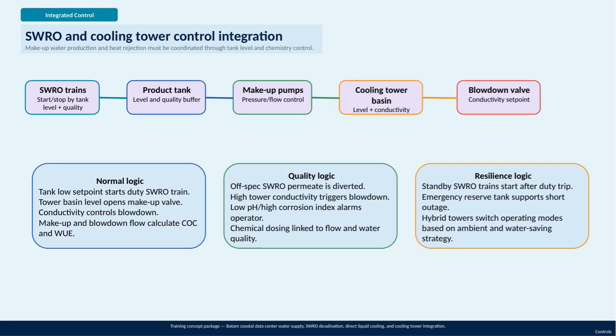The normal operating logic activates a duty SWRO train when tank levels fall below a set point, opens a makeup valve when tower basin levels drop, and uses conductivity to control blowdown flow. This coordination enables calculation of cycles of concentration and water use efficiency. In terms of quality control, any off-spec SWRO permeate is diverted to maintain standards, while high conductivity in the tower triggers blowdown to prevent scaling. Low pH or high corrosion index conditions trigger alarms, and chemical dosing is dynamically adjusted based on flow and water quality to protect equipment. Finally, resilience logic enhances system reliability. Standby SWRO trains can start automatically if a duty train trips, and an emergency reserve tank supports short outages.